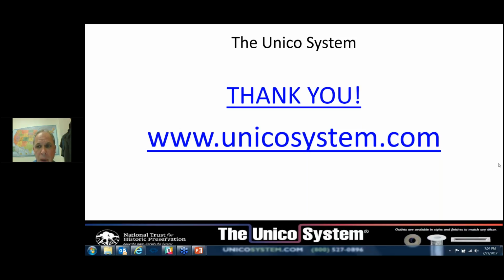It can be done two different ways. A couple of years ago we entered into an engineering and manufacturing partnership with an Italian firm called Argo Clima, who makes one of the most robust and energy efficient outdoor heat pumps in Europe, and they also manufacture all Panasonic equipment for Europe. But their own product, the I-Series, is a great match to Unico, so we've been importing that and hooking it to Unico systems. What's great about it is that outdoor unit works down to even colder temperatures than standard heat pumps do. At -10 degrees you're getting 65% of the original capacity of the unit, and you're still getting nice warm air. At 5 degrees you're getting 90% of the capacity. You don't get that with any other product.